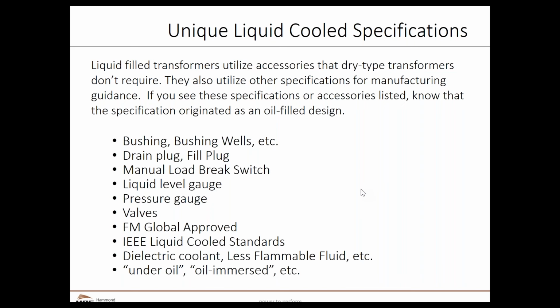Valves. FM Global Approved is an insurance agency that does a lot of work with commercial properties, especially in North America. They tend to have certain specifications for liquid filled transformers. So having something that might meet their overall specifications will help standardize what the insurance policy is for that area. We will see certain IEEE standards that are specific to liquid filled versus dry type. Again, we might see things like dielectric coolant, less flammable fluid, under oil or oil immersed. All of these terms and conditions are really reflective of a liquid-filled transformer. And by the way, there is no dry type equivalent. So when somebody, again, hands us an oil spec, we can't meet this. Probably don't need them, but again, can't meet it.